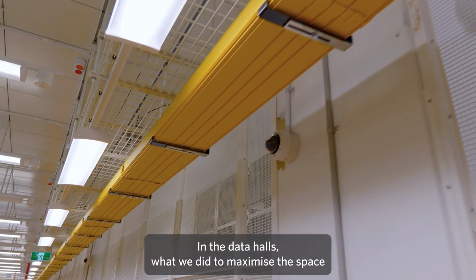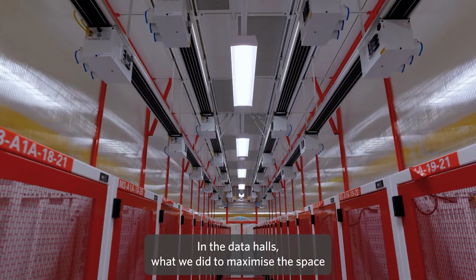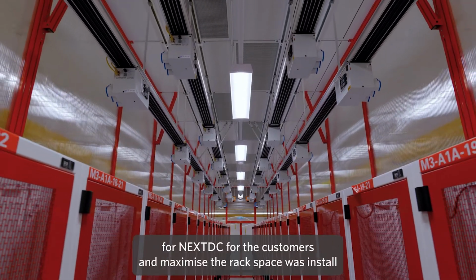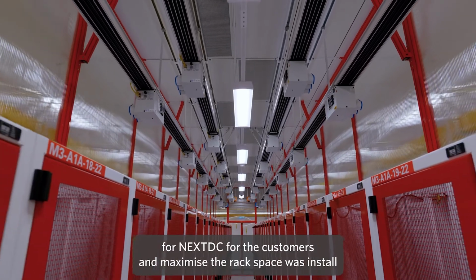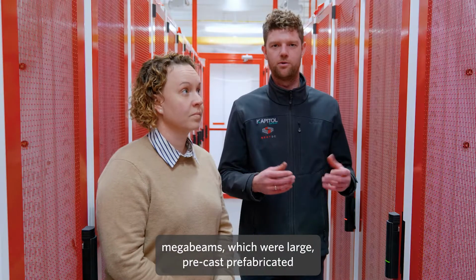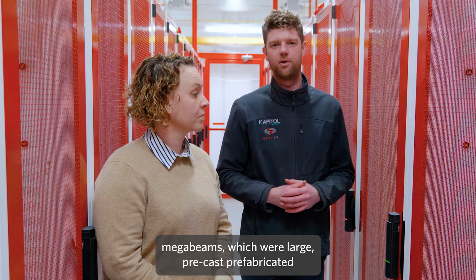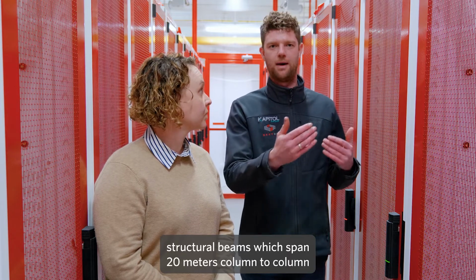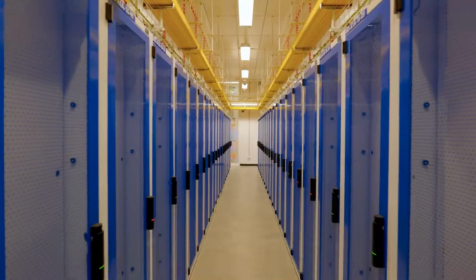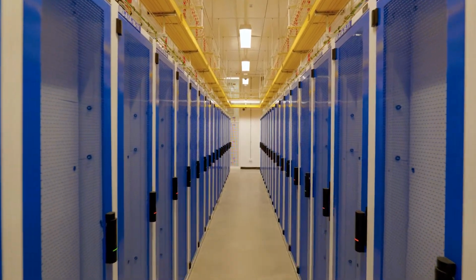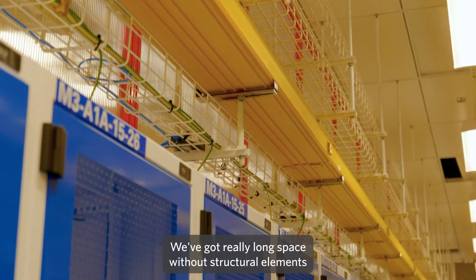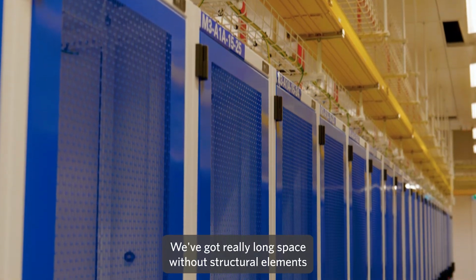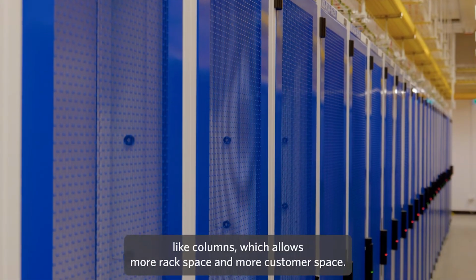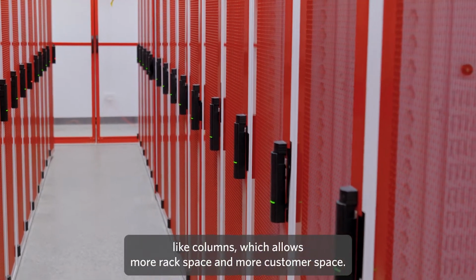In the data halls, to maximise the space for NEXTDC's customers and maximise rack space, we installed mega beams, large precast prefabricated structural beams that span 20 metres column to column, really opening up the space within the data halls. So you can see where we are now, we've got really long space without structural elements like columns, allowing more rack space and more customer space for NEXTDC.